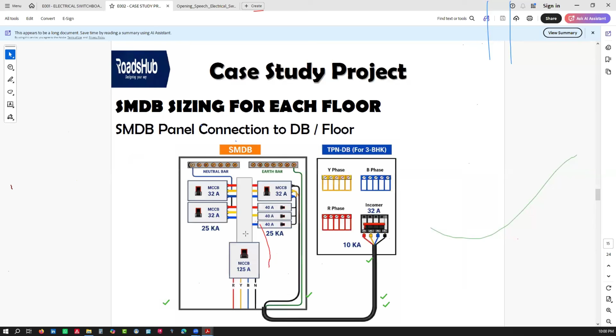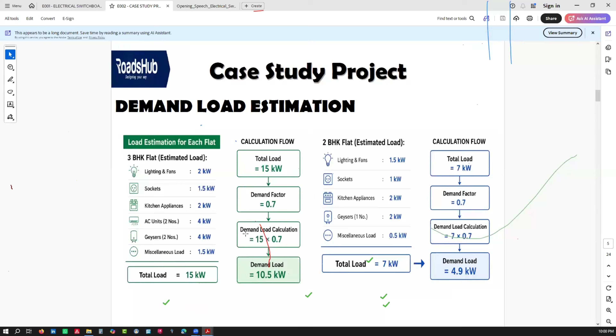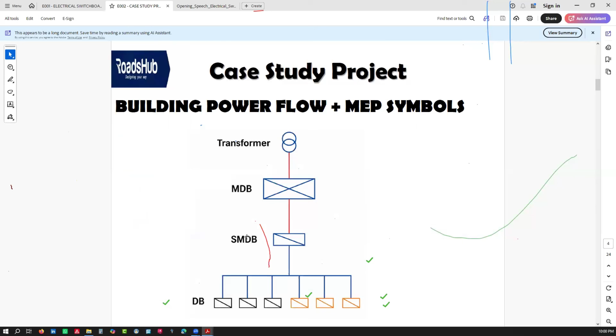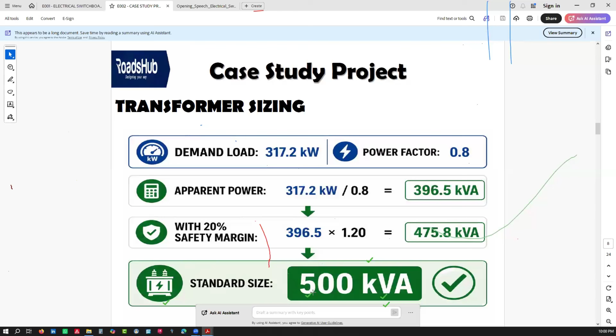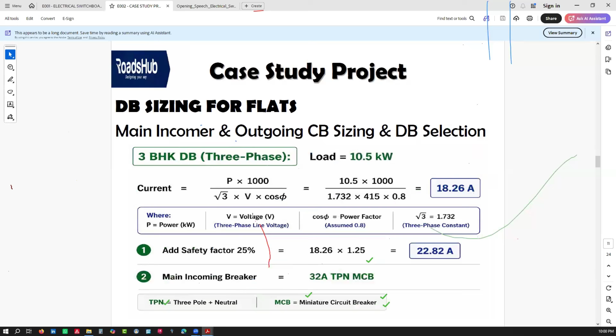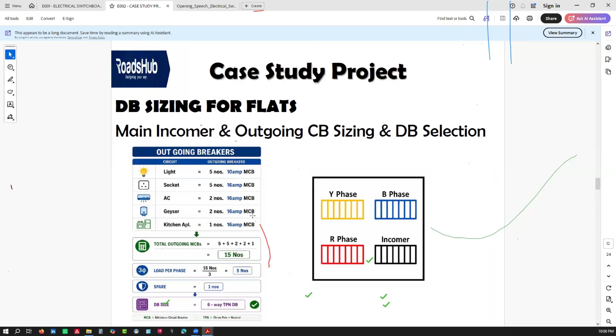You remember we selected a transformer here and we selected a 500 kVA. Now you use this because we had put a safety margin. So the incoming breaker that will be supplied by the transformer, you need to go again into the 3-phase current formula, do a 20%, and then you select your main breaker.